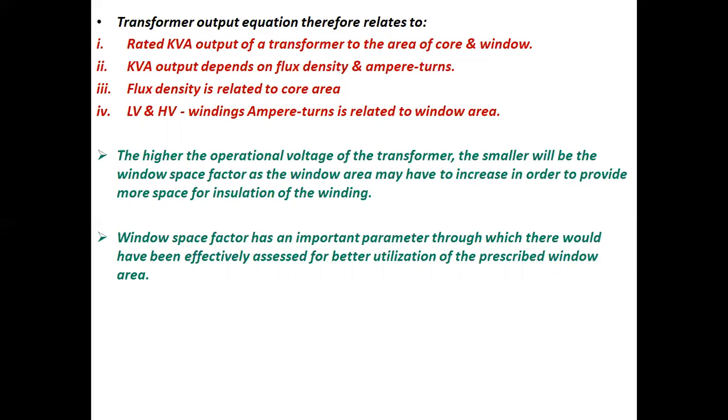Important points to be noted: 1. The higher the operational voltage of the transformer, the smaller will be the window space factor, as the window area may have to increase in order to provide more space for insulation of the winding. 2. Window space factor is an important parameter through which the utilization of the prescribed window area can be effectively assessed.